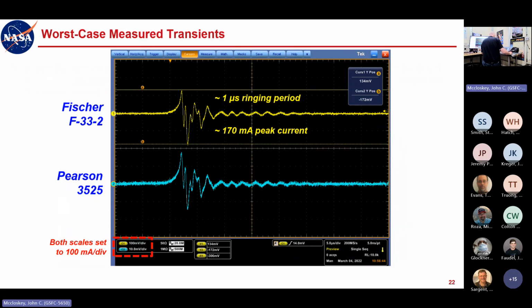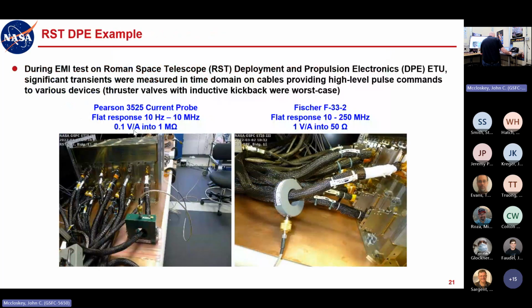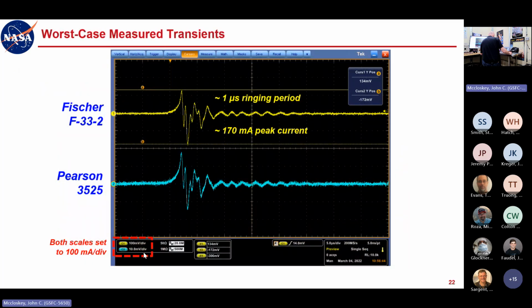Here are the waveforms, and just note that both scales are set to 100 milliamps per division. The yellow trace is 100 millivolts per division. That's the Fisher probe, the one ohm transfer impedance, so 100 millivolts equals 100 milliamps. And then the Pearson probe is 0.1 volts per amp, or 10 amps per volt. So at 10 millivolts per division, that's the same as 100 milliamps per division, and it's going into the 1 megohm input. That transfer impedance goes down by a factor of 2 if I go into the 50 ohm input. So there are all these things to keep in mind. But anyway, I know I'm looking at these two on an equivalent current scale.